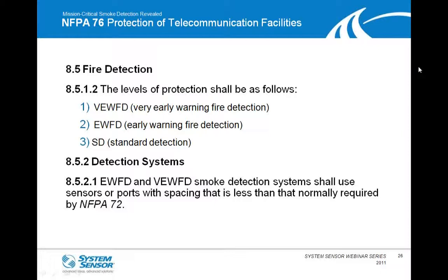And then finally, early warning or very early warning fire detection smoke systems shall use sensors or ports with spacing that is less than normally required. So much like NFPA talks about with high velocity areas, you need to reduce the spacing. In NFPA 76, it also talks about reducing that spacing. And again, remember that whether you're using a spot type detector or sampling points, either way that's basically viewed as a point of detection. So that spacing needs to be reduced to meet early warning and very early warning. And we'll go into more detail on how that's accomplished.